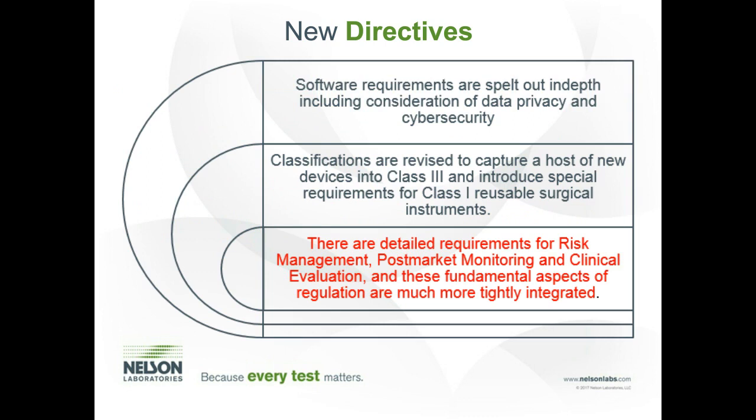So the first one is that whole new devices are classified into class 3 and other classes. And this means that the risk of these devices has been reevaluated. So we need to remember that when we're doing a biological evaluation plan on what the risk of these devices is per that individual notified body or regulatory agency that we're looking at. But in these new directives, there are detailed requirements for this risk management process. And once again, I know we keep on saying risk, but I just want to let you know that they are tightly integrated in this regulation, the aspects of risk assessment. So please be aware that you will have to have a risk assessment.